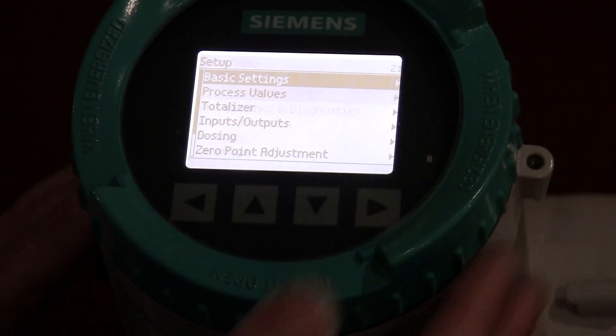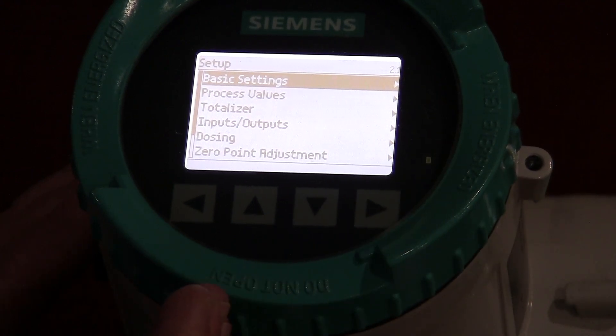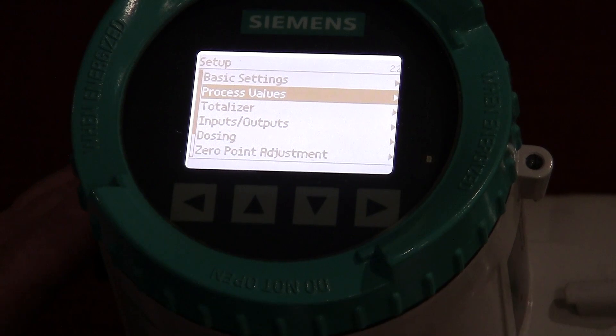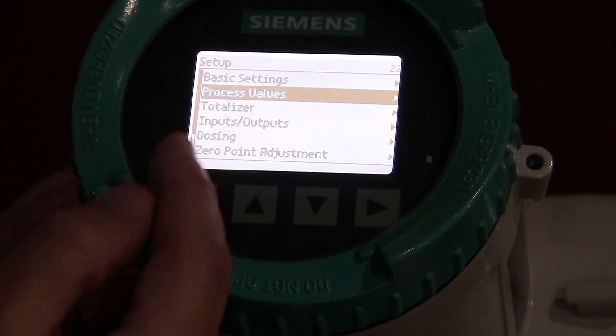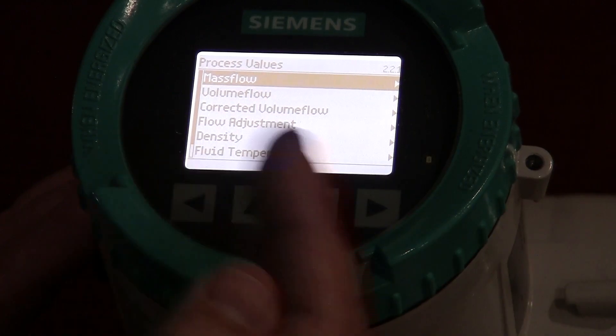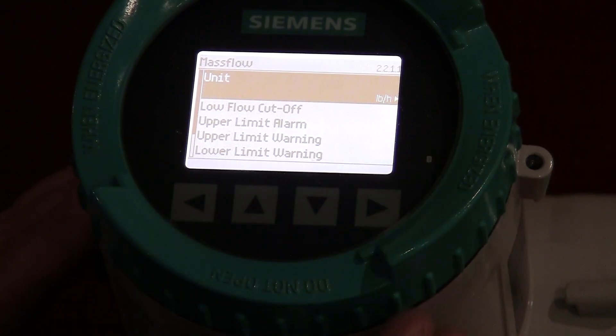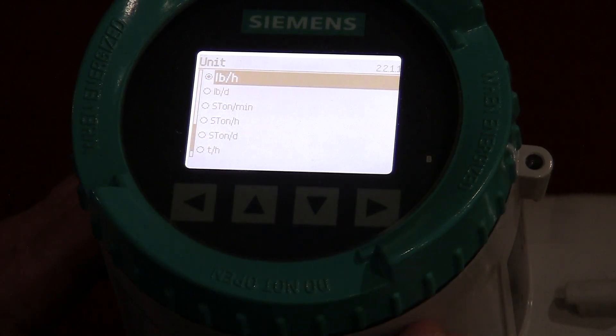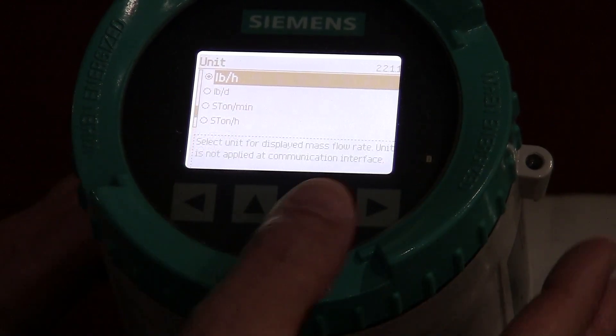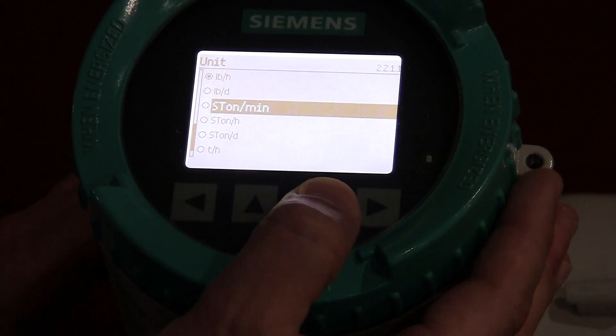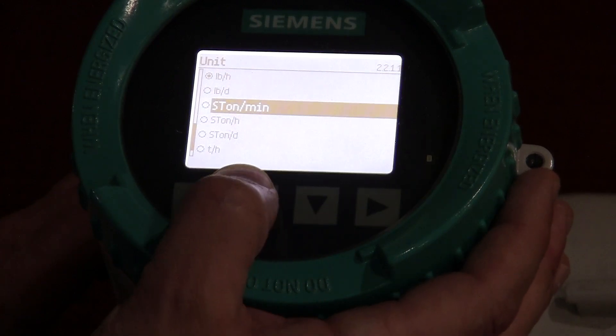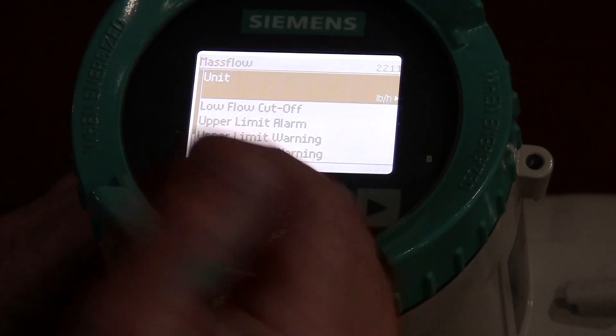Now, some of your screens might be different depending on the firmware version on your particular transmitter, because that firmware gets updated from time to time. But basically what you want to do is establish what you want the unit to read out in. So if I go to setup and go into process values, the first thing you'll see is mass flow, and this is where you're going to establish what engineering units you want to use. Right now I'm in pounds per hour, but to change that you simply hit the right arrow, drop into your menu, and you can arrow down to the different settings. I'm going to leave mine in pounds per hour. Once you have selected what you like, just hit the enter key and it will accept that value, and you'll see what the value is stored on the right-hand side.